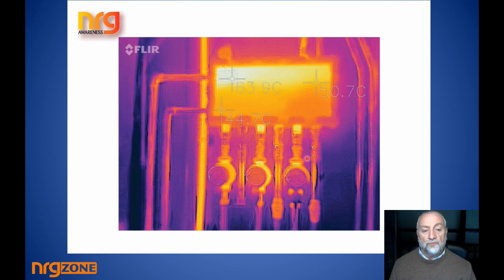So now you can see with a thermal imaging camera, for example, as this system is starting to heat up, there was an issue with this job, because what we noticed is that the heat from the return coming back here, this pump was set too high and the boiler pump wasn't set high enough. By turning it on, we could see immediately there was some bypass water, water going backwards up through the bypass. So we were able to turn up the boiler pump a bit stronger, and you really don't care what's happening once it's below this level here. It's this point here that you want heat to. Anything beyond that doesn't matter, because it's flowing that direction anyway.